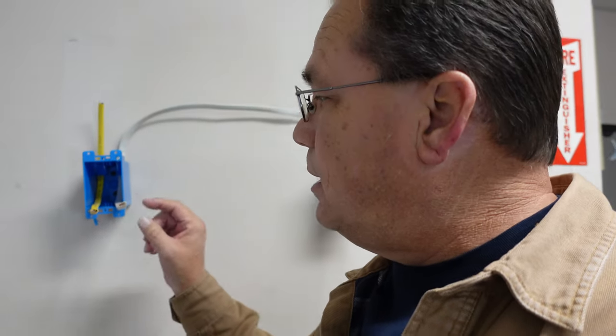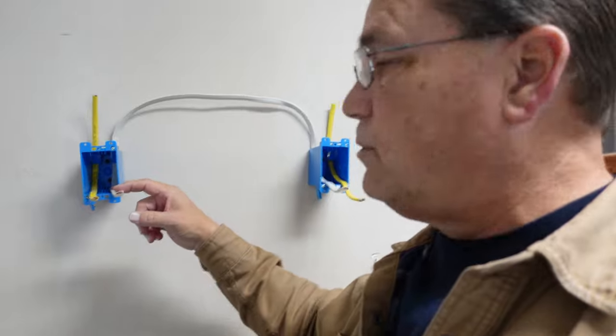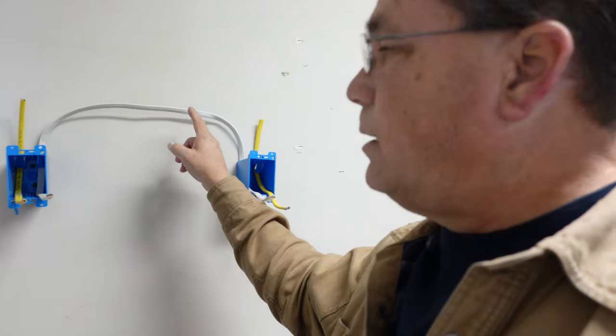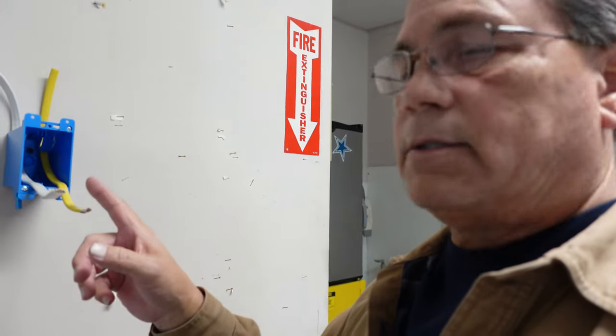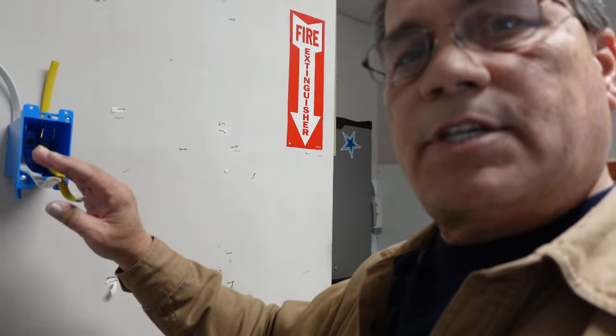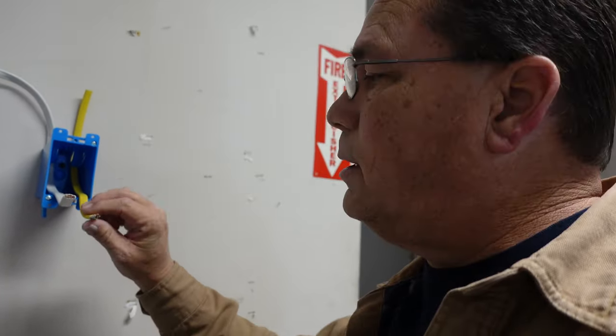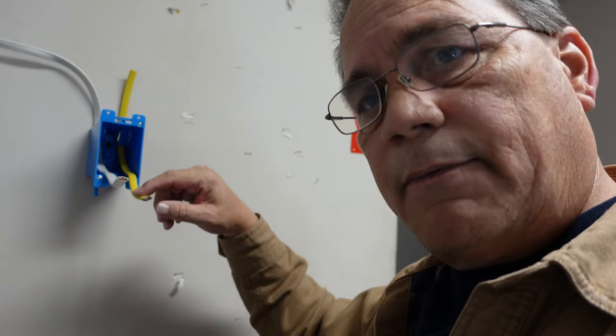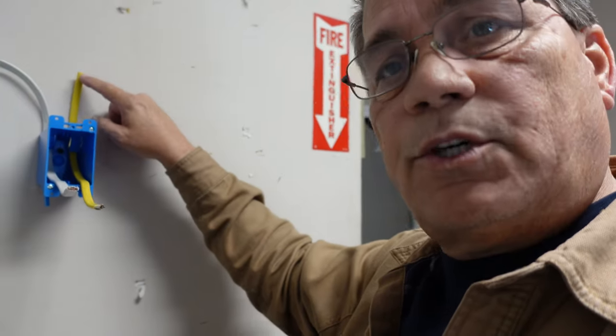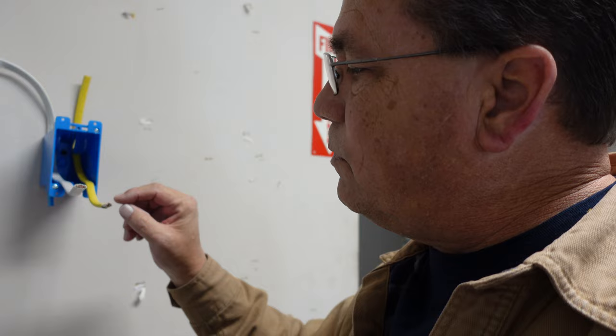The other two screws on your switch are brass. They're the travel legs. They get the black and the red off of your travel circuit that goes over to the other box. And then you're going to do the same thing on the other box. The difference is that you're putting power out of this terminal, or out of this wire, and it's going to a light fixture. But the concept is the same.